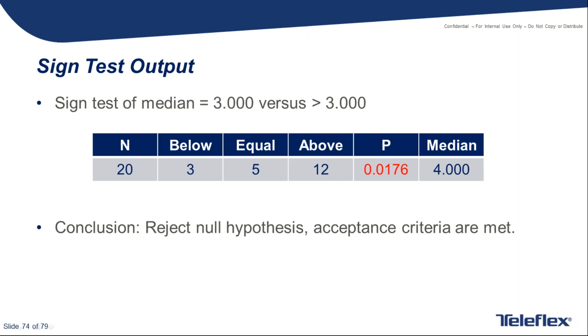So if you test, say, 5 of something, all 5 of those have to be above the median in order for the acceptance criteria to pass. But if you test 10, then you're allowed to get a certain number of 3s and 1s and 2s. And so that's why developing the table using statistical software and the sign test application is good to do ahead of time, so it's in black and white. And you certainly can do the analysis afterwards. If you tested 32 of something, and you have a certain number of yeses, nos, and no opinions, or 4s and 5s and 3s and 1s and 2s, you could definitely do the analysis. You need an engineer or a statistician to help with that if necessary, but it's definitely a valid methodology.